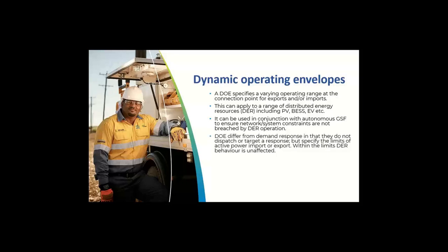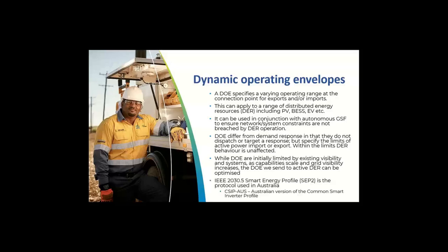Dynamic operating envelopes differ from demand response in that they do not dispatch or target a response, but specify the limits of active power import or export. Within the limits, DER behavior is unaffected. While dynamic operating envelopes are initially limited by existing visibility and systems, as the capabilities scale up and grid visibility increases, our dynamic operating envelopes will be enhanced and continue to improve.